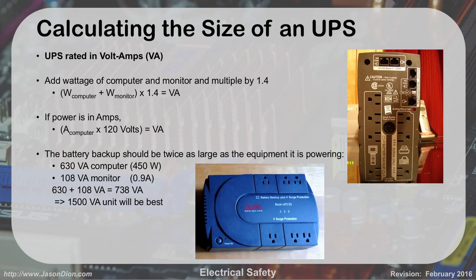A good example: here I have a 630 volt amp computer, which has a 450 watt power supply, and a 108 volt amp monitor, which had a 0.9 amp draw. We'd use the bottom calculation with the 0.9 amps times 120, giving us 108. On top, we have our watts for the computer times 1.4, giving us the 630 volt amps. Add those together and that gives us 738 volt amps. We want to multiply that by 2 and get something around 1500 volt amps, which would be something like this small UPS at the bottom, which you could buy for about $50 to $100 at Best Buy.